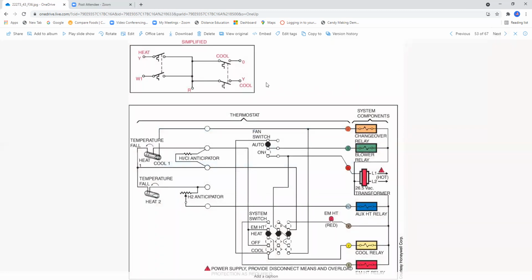Okay, this is a thermostat up here. We're utilizing the O terminal. And notice here, we're in the heat mode. Emergency heat, in this case, is energized because the slide switch is energized. In this case, the emergency heat relay has energized the strip heat. The auxiliary heat package consists of 1 or 2 or 3 elements. Don't forget the heating elements have sequencers to prevent them from all coming on at the same time.